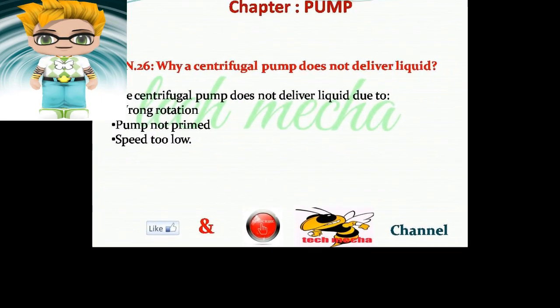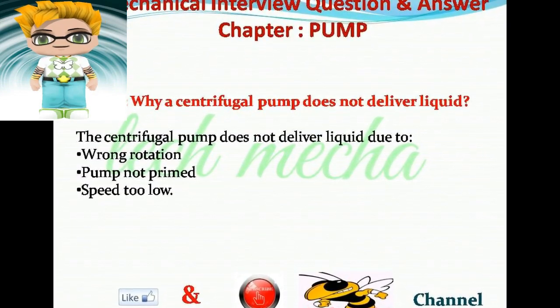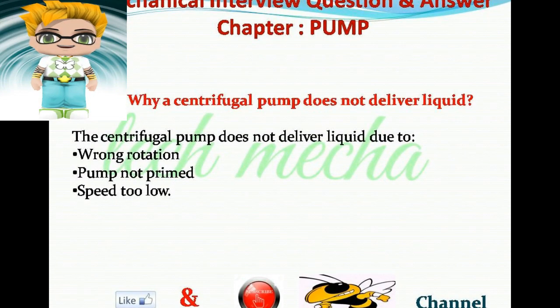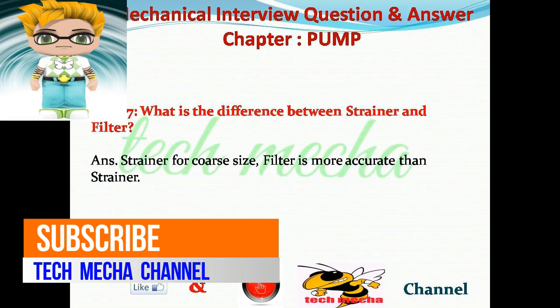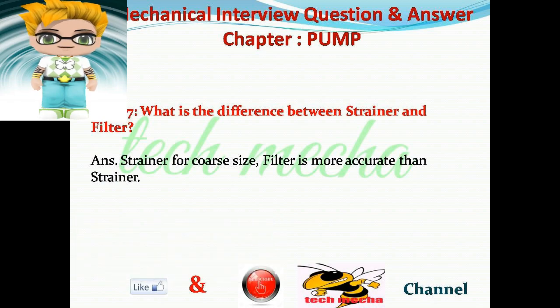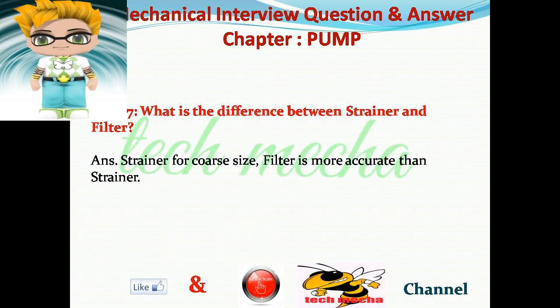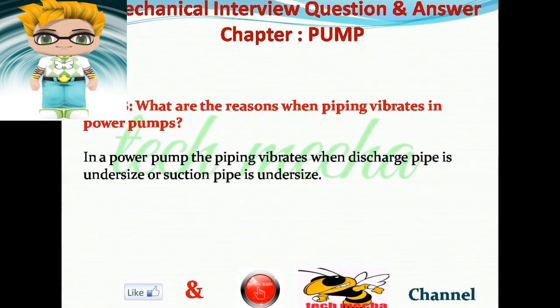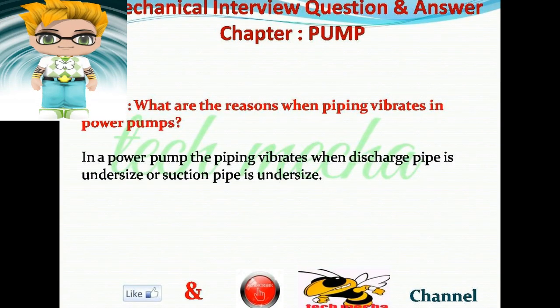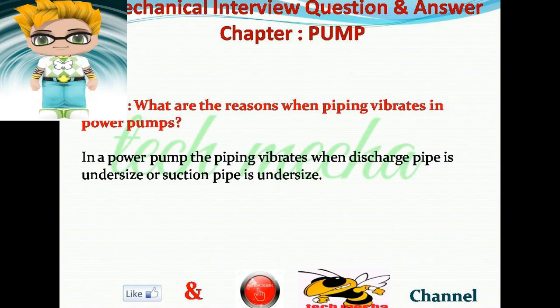Question number 26: Why does a centrifugal pump not deliver liquid? Answer: The centrifugal pump does not deliver liquid due to wrong rotation, pump not primed, or speed too low. Question number 27: What is the difference between a strainer and a filter? Answer: A strainer handles coarser sizes; a filter is more accurate than a strainer. Question number 28: What are the reasons when piping vibrates in power pumps? Answer: In a power pump, piping vibrates when the discharge pipe or suction pipe is undersized.